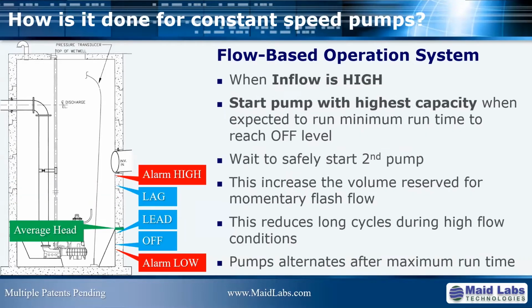So let's see now, when the flow coming in is high, what do you do? First, you start your pump with the highest pump capacity, and you don't wait to get to the lead level to start your pump. What you do is that as soon as you know that your pump will be running, let's say 2 minutes, because that's what you would have specified, you start your pump.